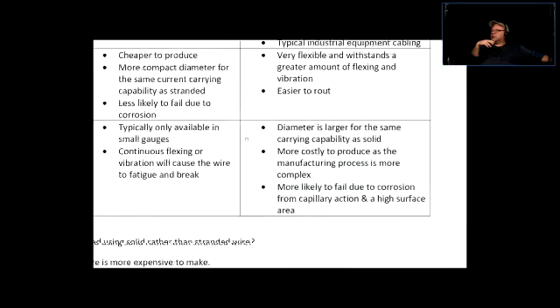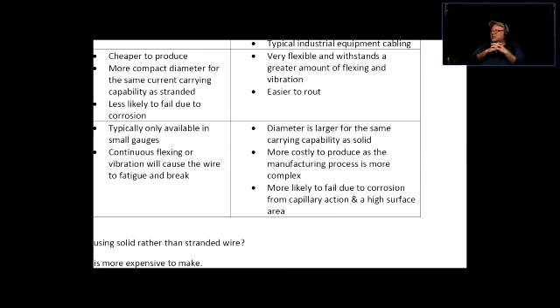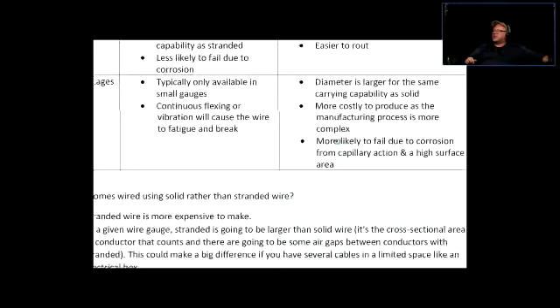The diameter is larger for the same current carrying capacity than the solid is. So if you run one or two of those wires, no problem. But if you have a whole bundle of them, then yeah, it's going to take up more space, right? And things do add up quickly when you're pulling multiple wires, installing multiple wires. But also, another disadvantage is it's more likely to fail due to corrosion from the capillary action and a high surface area. All right. So basically, what I explained to you.